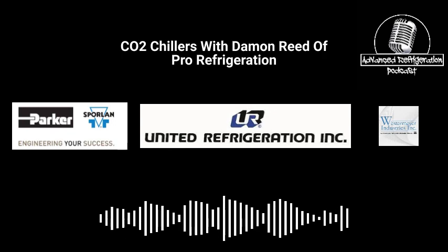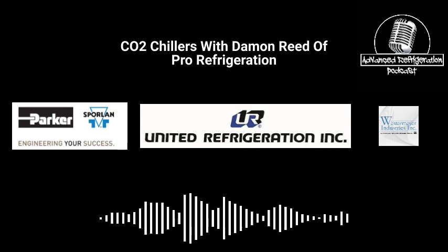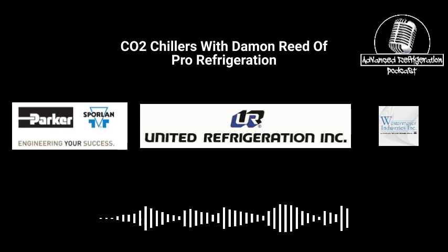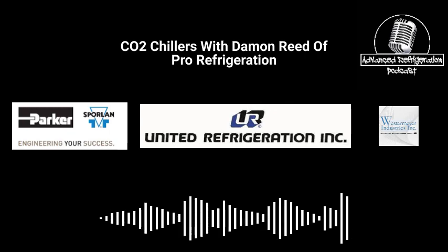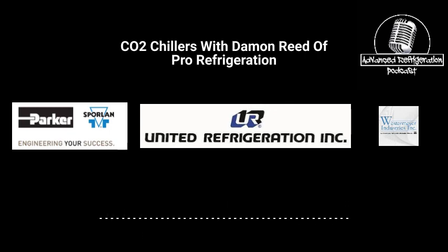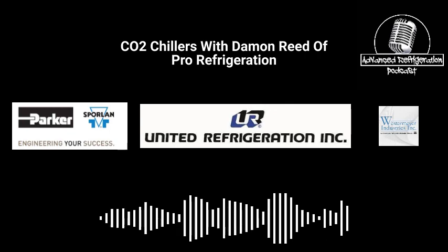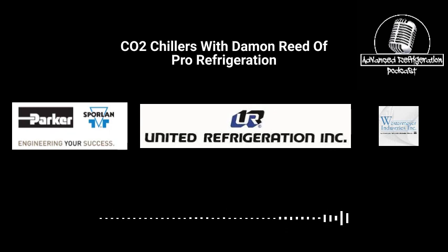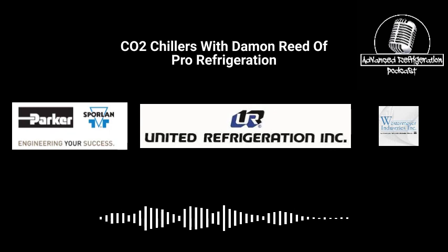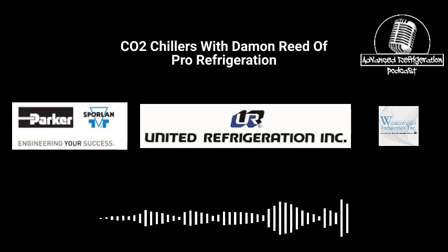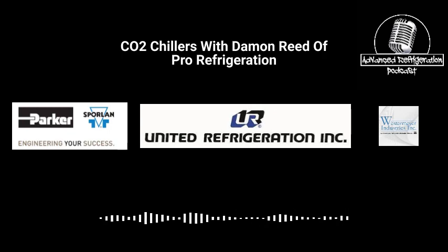This was their installation, the end of the job site, cleaning everything up and making sure it's in ship shape. So your TD on your air cooled condenser or gas cooler, what are you guys trying to maintain on that? Well, it depends on whether I'm subcritical or transcritical, right? What I'm really controlling everything to is my gas cooler outlet temperature, which I'm looking for around 70 degrees, somewhere in that range.